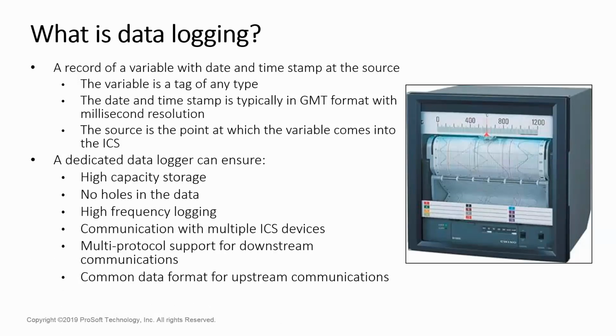A dedicated data logger with high capacity has a number of benefits, including high capacity storage, which means no holes in your data. It also enables high frequency logging, required for certain applications. A dedicated logger can talk to multiple devices, meaning a single product can communicate with different control systems and bring all the data together, supporting multiple protocols downstream. So you could have a PLC that talks Ethernet IP and another that talks DNP3, but a single gateway data logger could communicate with both and bring the data in, giving you one data format for upstream communications.